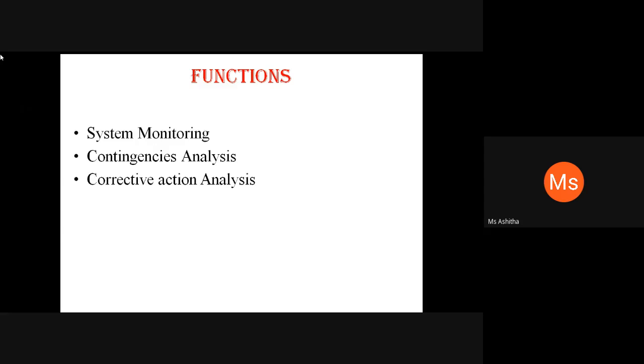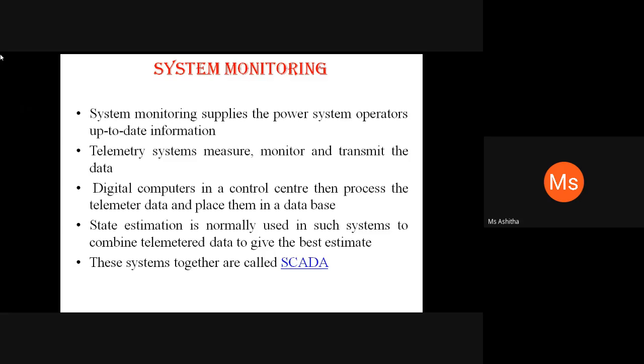So system security comprises three major functions that are carried out in an energy control center. One is system monitoring, second contingency analysis, third corrective action analysis. System monitoring supplies the power system operators or dispatchers with pertinent up-to-date information on the condition of the power system on a real-time basis as load and generation change.